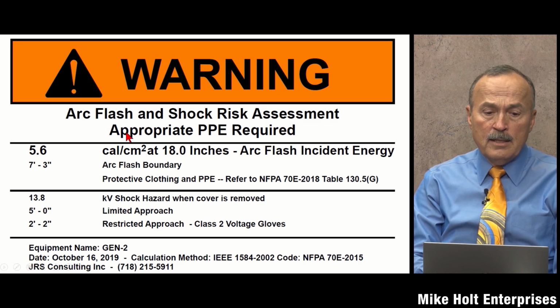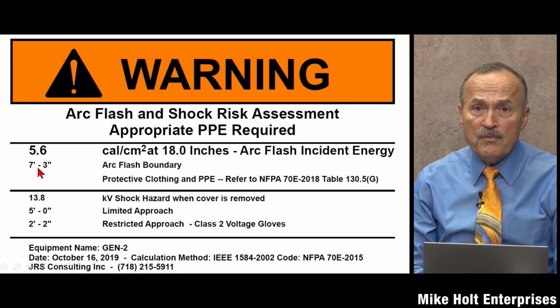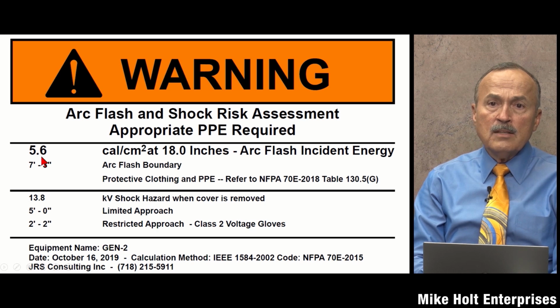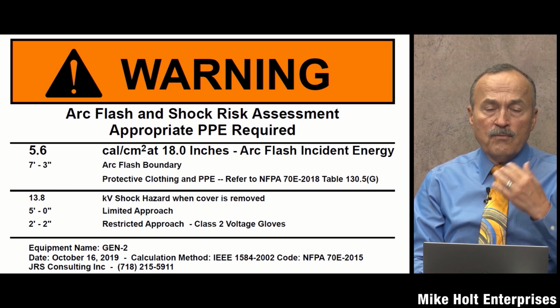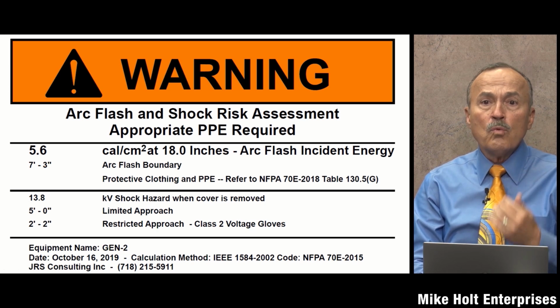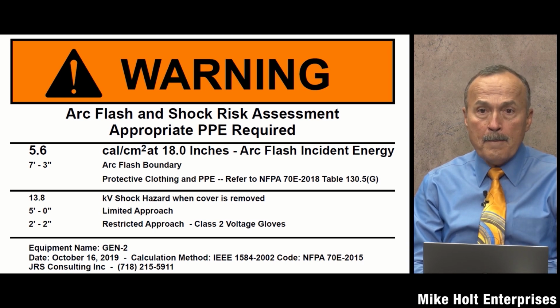And that tells me, okay, Ryan, when you get out there and see this label, it says if you're going to be within 7 feet 3 inches and that cover is off, then you need protective gear with 5.6 calories per square centimeter rated clothing.